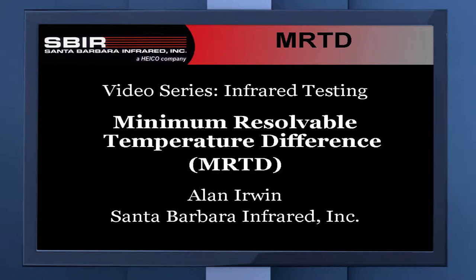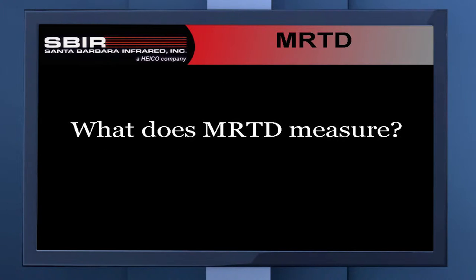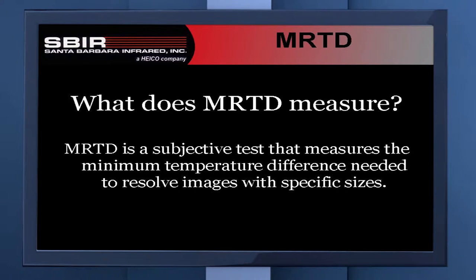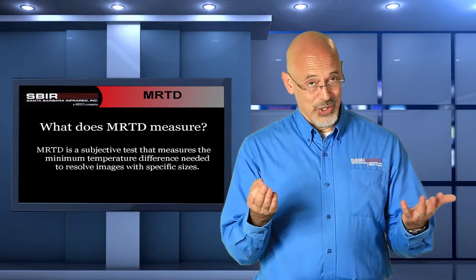Hi, Alan Irwin from Santa Barbara Infrared, and in this video, we're going to be talking about minimum resolvable temperature difference, more typically known as MRTD. So what does MRTD measure? MRTD is a subjective test that measures the minimum temperature difference needed to resolve targets with specific sizes. So let's talk about what all those components are.